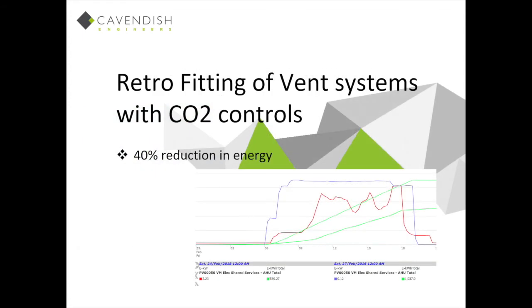Let's look at the detail of the analytics that Mark was picking up. If you look at the blue line in that CO2 vent system, that's how the air handling unit used to operate - it came on in the morning, ran all day, went off in the evening. After the retrofit of CO2 controls, you can see it actually follows the occupied load - the air handling unit only operates to provide ventilation to the people on the floors.